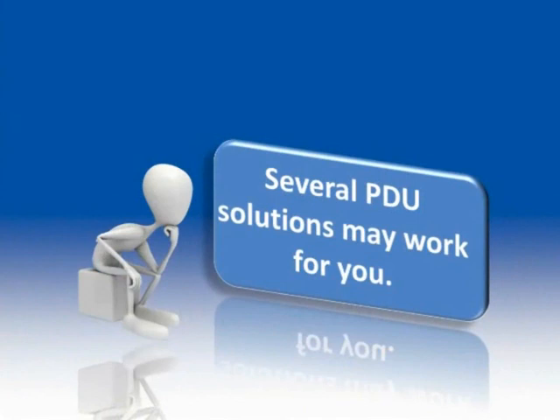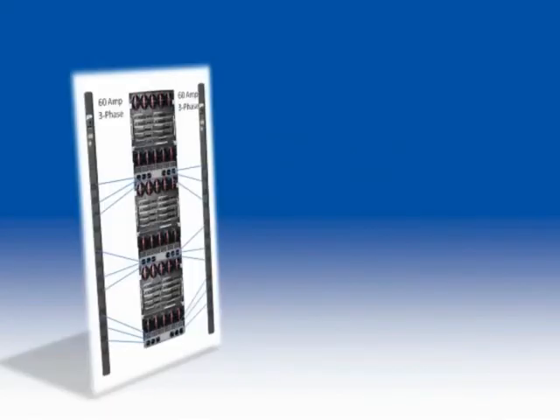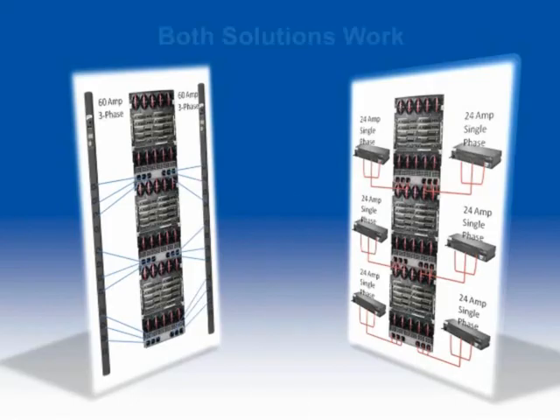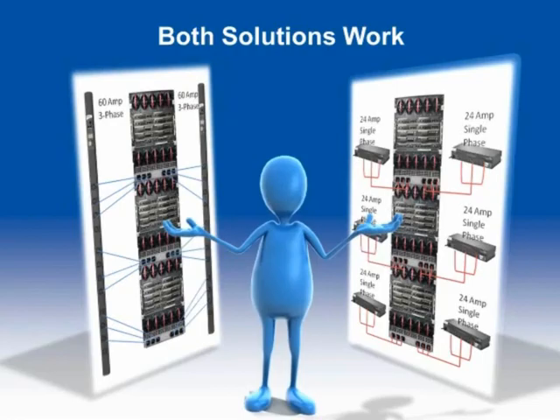When putting together your PDU solution, there can be several different yet correct solutions that work for you. The solution you choose will be determined by what power the data center has access to. Example 1 shows a solution deploying 3-phase PDUs — this uses fewer power drops, fewer breakers on the power panel, and takes up less room in the rack. Example 2 shows a facility that cannot provide 3-phase power, requiring more power drops, more breakers on the breaker panel, and additional room on the rack. Example 1 clearly shows that 3-phase power is more efficient, delivering more power more efficiently. However, both solutions have your servers up and running.